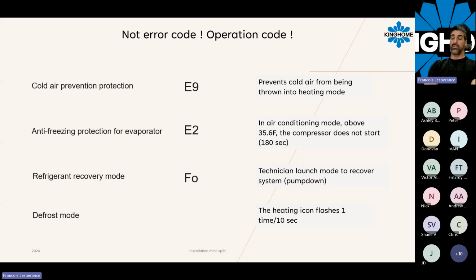So whenever you have a phone call by your customer saying, "Hey, I don't know why my sun icon is flashing for 3-4 minutes, and I don't know why." Well, it's just because the system is now in defrost mode. Sometimes you might see H1. H1 is a second state of defrost. It's a fast defrost operation. So sometimes you can see H1 or just a heating icon flashing.